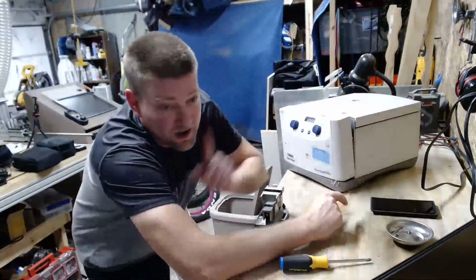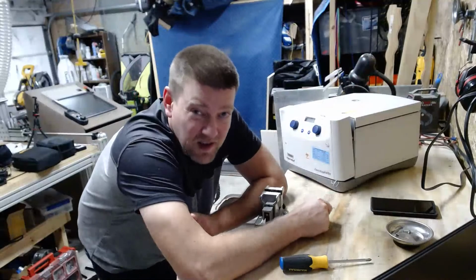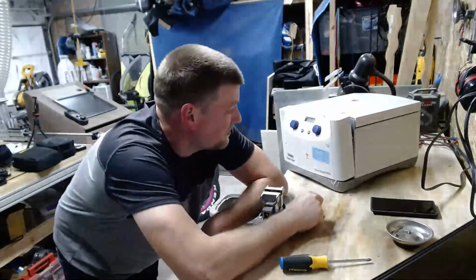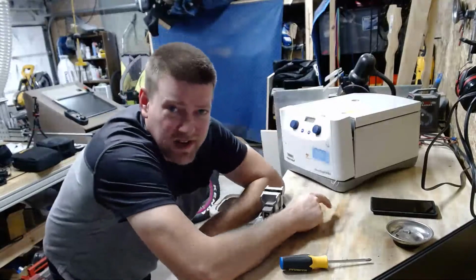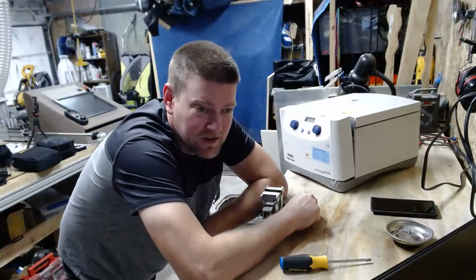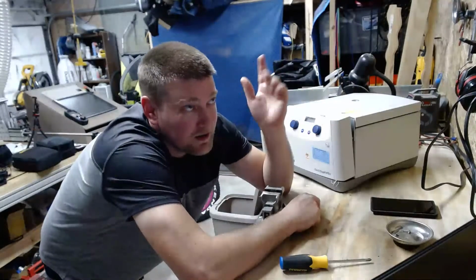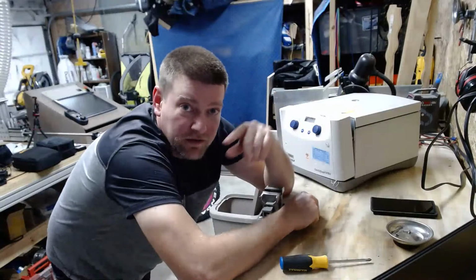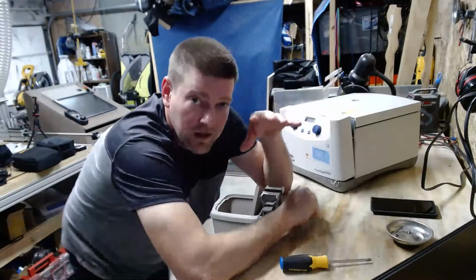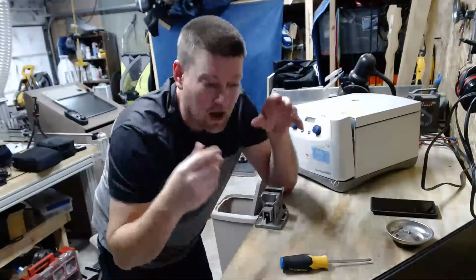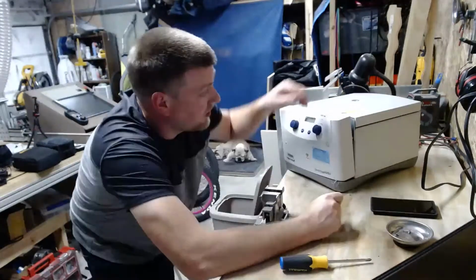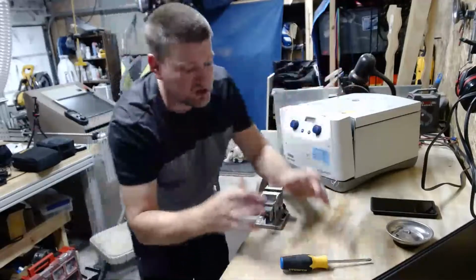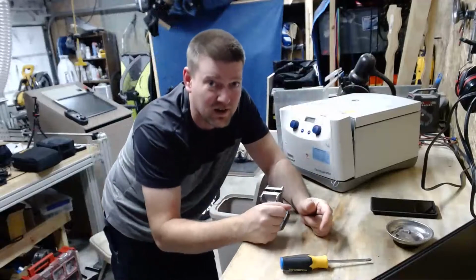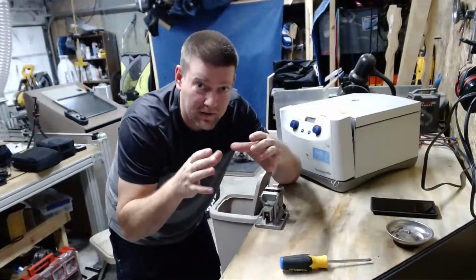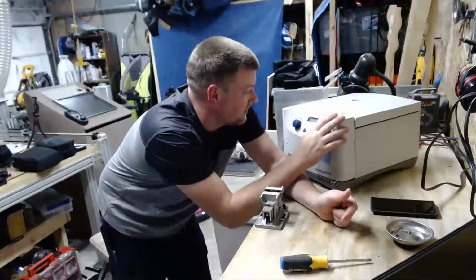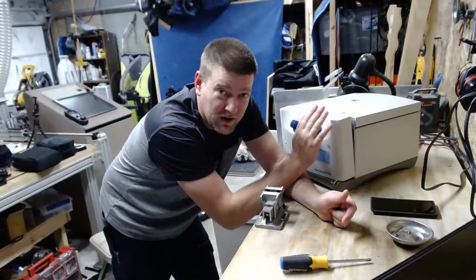Centrifuges, it is not always in RPM, or revolutions per minute. Sometimes it's in RCF, or relative centrifugal force. RCF is a formula based on the amount of centrifugal force that unit can generate. Things that affect that are your speed, the sample size, and your distance from the center point. So on a smaller centrifuge, it has to spin way faster to obtain the same RCF as a larger centrifuge. This one here goes up to, was it 4,500 RPMs?